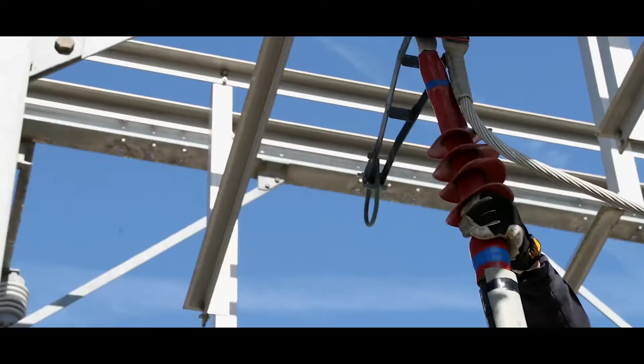We've got our clearance order released and our grounds removed, mid equipment in the clear. Now we're going to energize the high side of the mobile, and then we'll have dispatch test the controls of the low volt main. We'll close in over there, then we'll phase in above the low volt main of the sub.